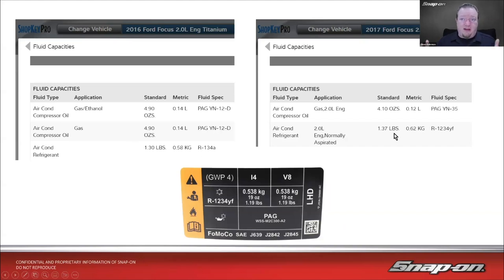That's where it comes into critical charge — we need to make sure we're charging exactly what it's supposed to have. So how do I know? Just check the label. If you don't have the label, go into your repair information and look up the proper year, make, and model. That would be the second best option, because I'd err on the side of the label, since sometimes things change mid-year that don't always get picked up. So always refer to the label first, then the repair information.